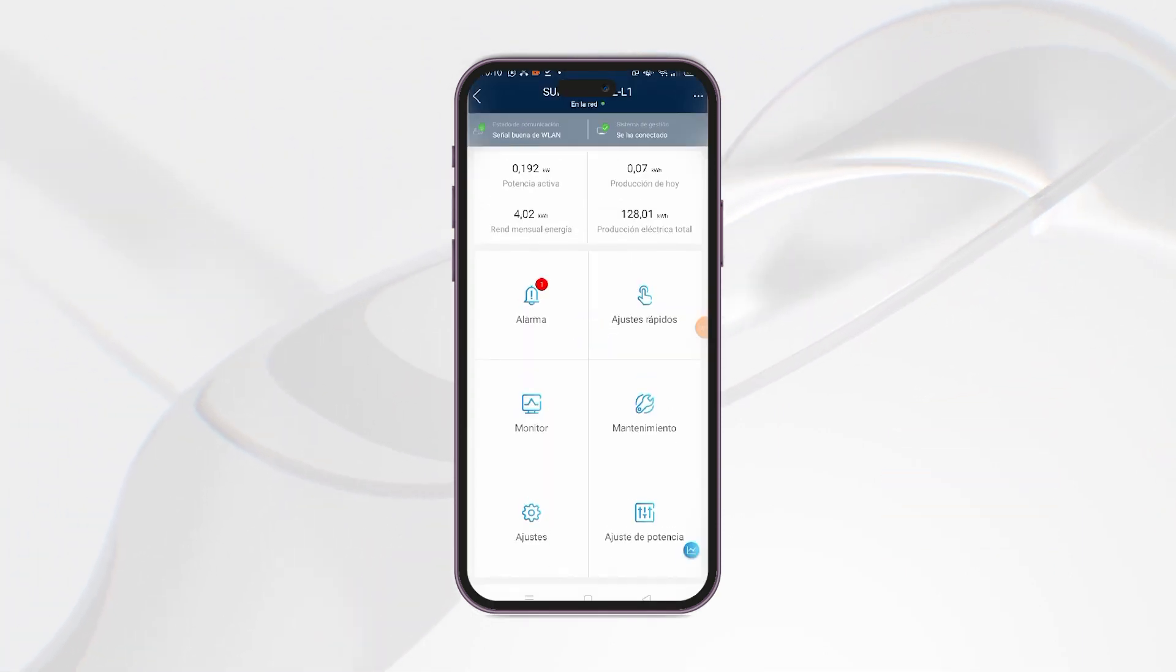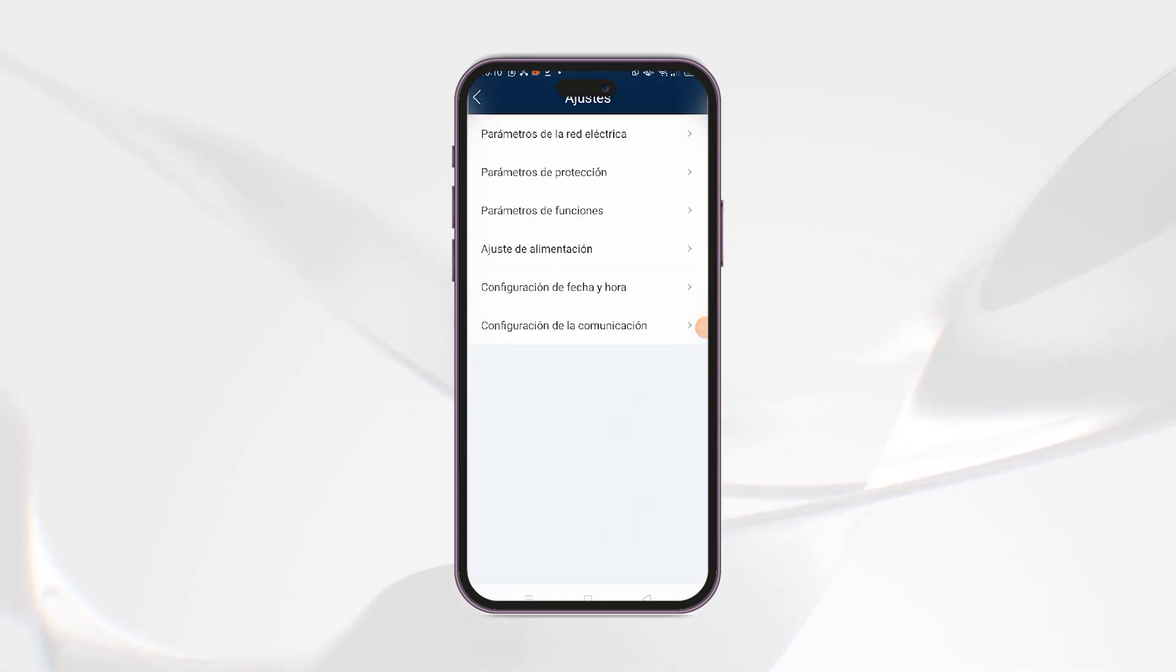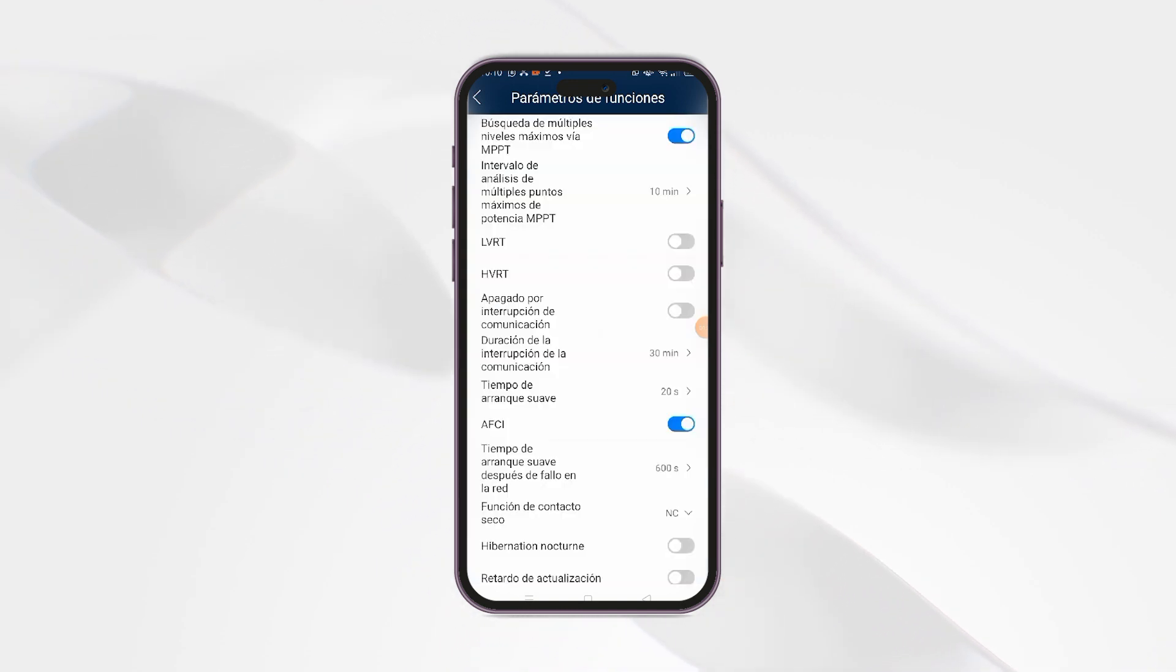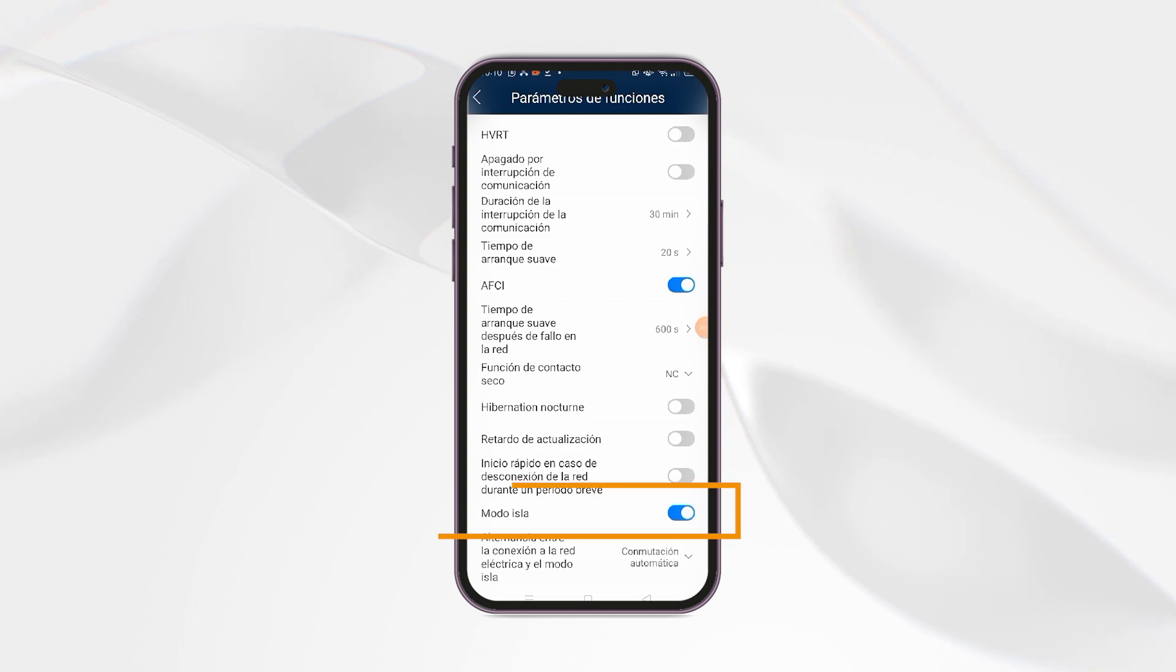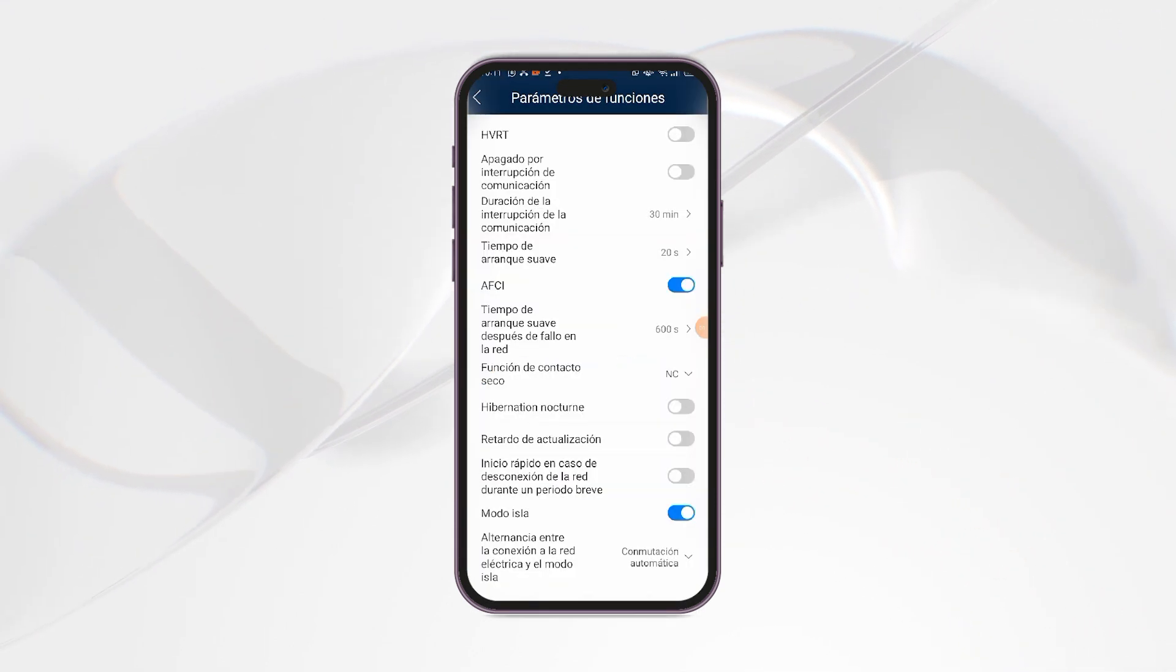Once inside, the following menu will appear. We go to the Settings section and select Function Parameter. In the list of parameters, we must activate Island Mode and configure the automatic switching in alternation between mains connection and island mode.